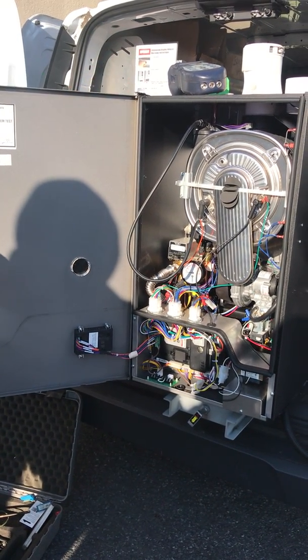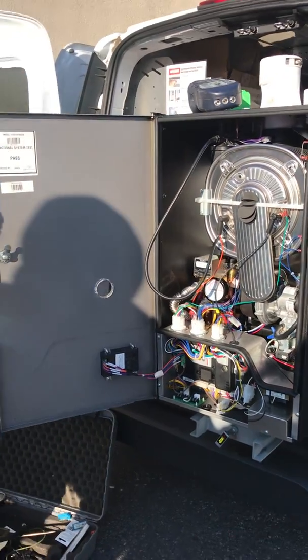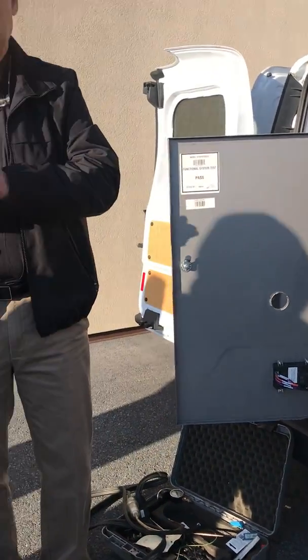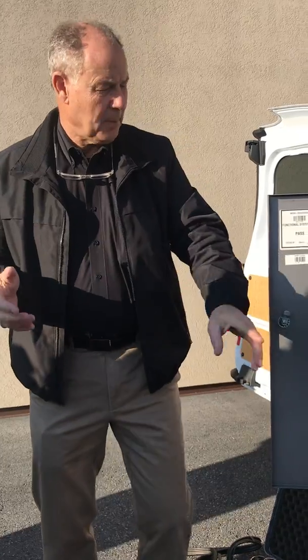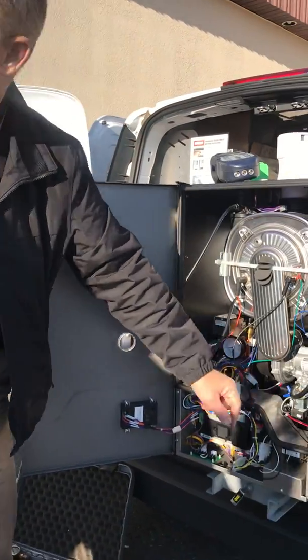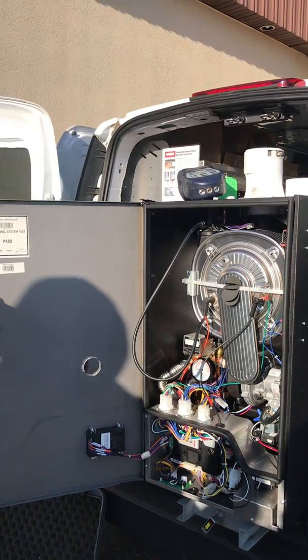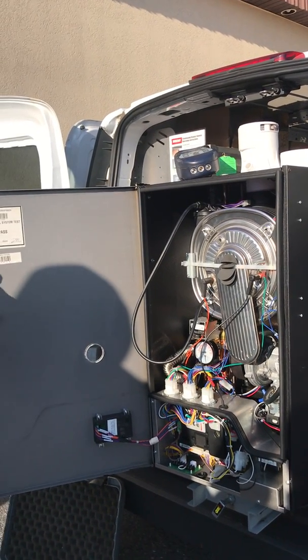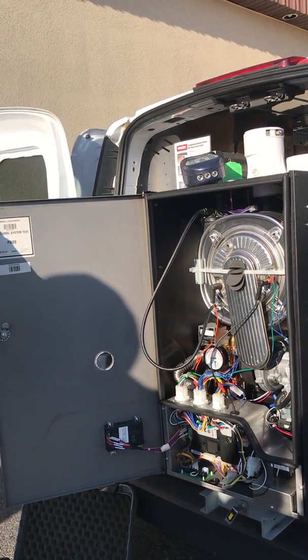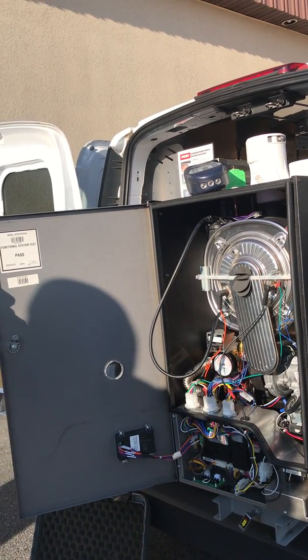Your combustion analyzer, we're going to check the exhaust. We turn it on. What you're going to find is it's going to be a little rich. Not bad. When you increase gas on an appliance or decrease, if I decrease gas on a regulator, do I usually screw it in or back it out? Decrease? No, it's taken out. If I decrease, I usually back out. Yeah. This gas valve, it's a needle valve. So you actually screw in. So I actually will take it half a turn in and check my combustion.